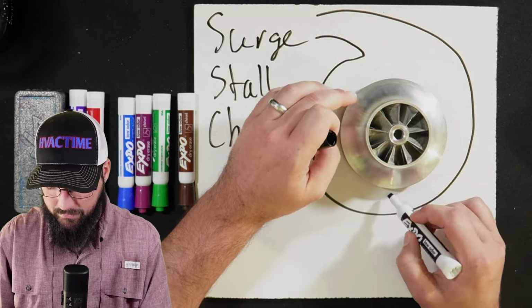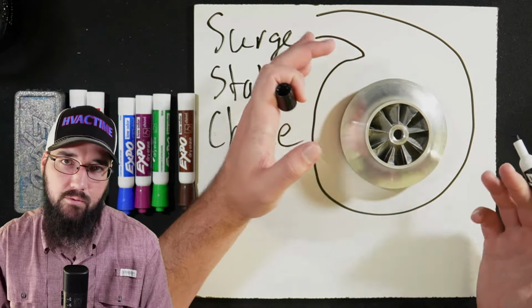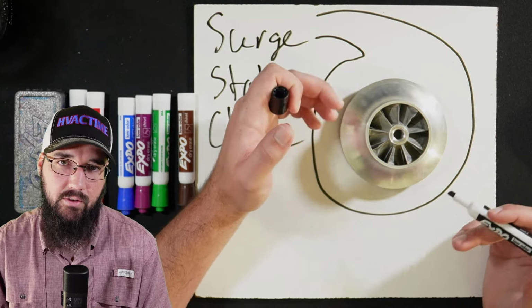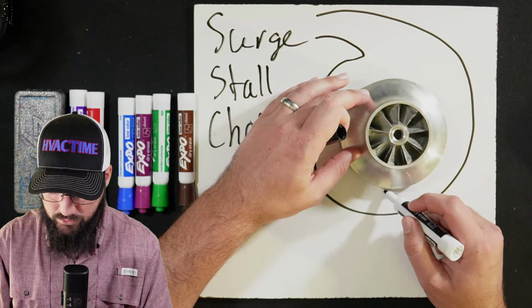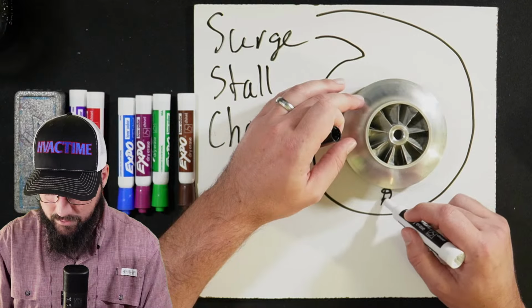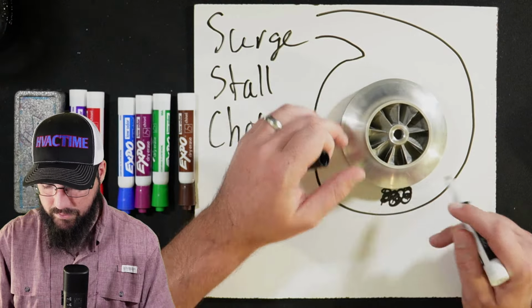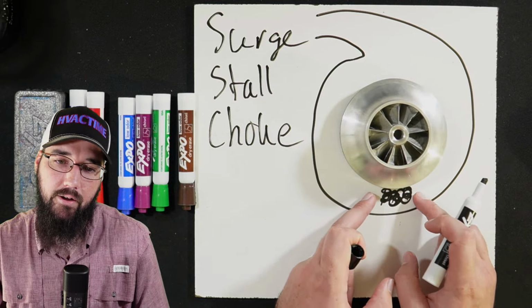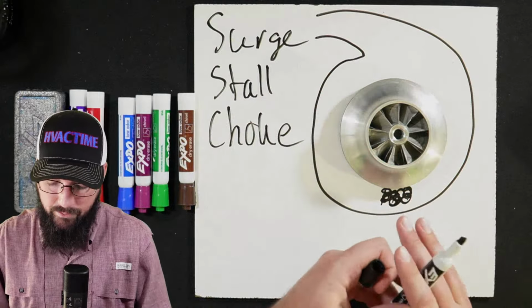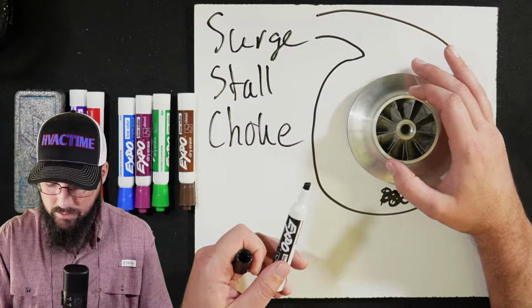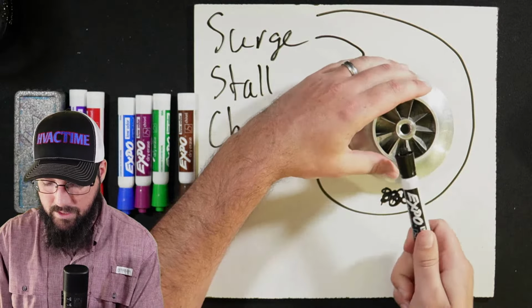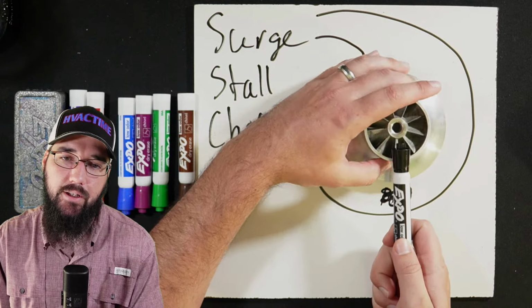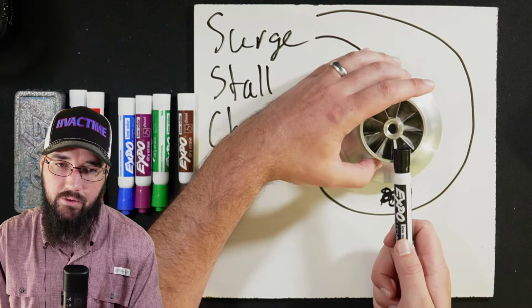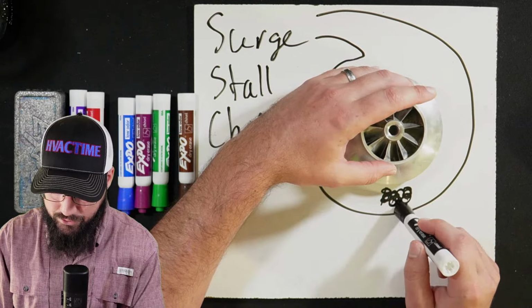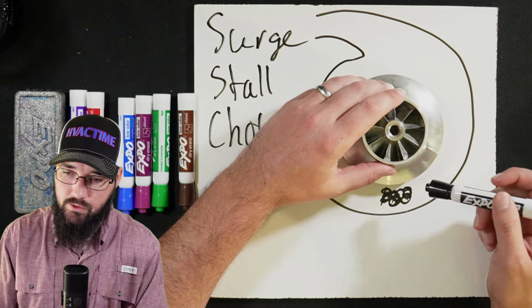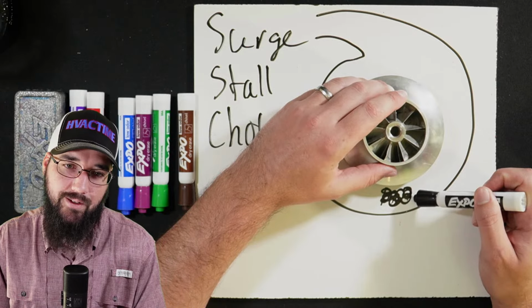because what's actually happening is, let's say surge is an accumulation of instability, which then leads to a reversal of flow. Stall is a more pinpointed section. So let's say right here, the impeller started struggling inside of the volute and the diffuser in this section. The rest of it was still stable and flowing. So as we're spinning, whichever vane aligns right here is the one that's actually stalling, and it's a rotating stall because the stall is correlated to the spot in the diffuser that is having trouble.